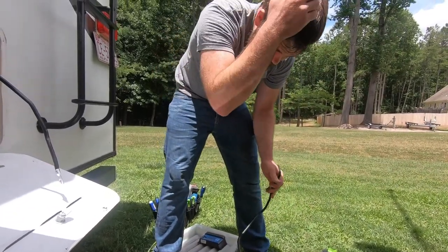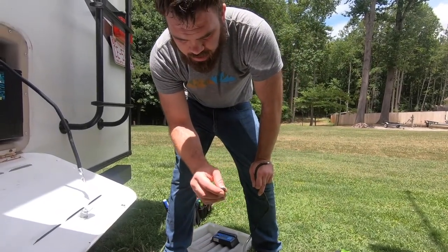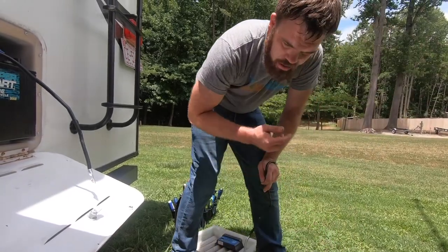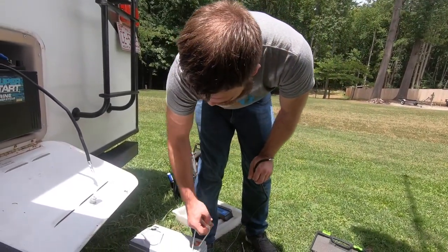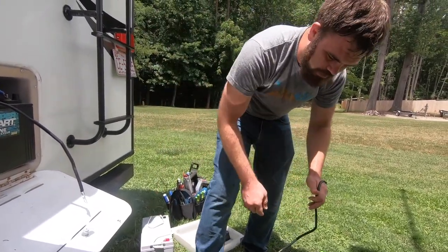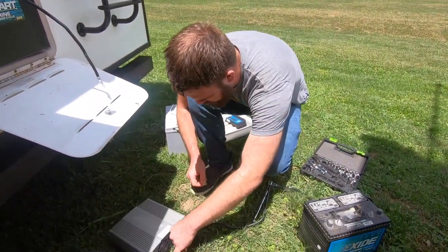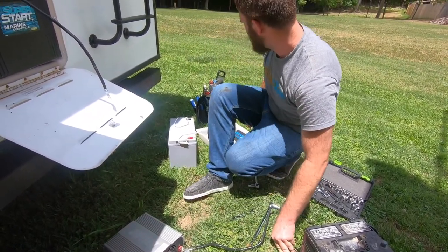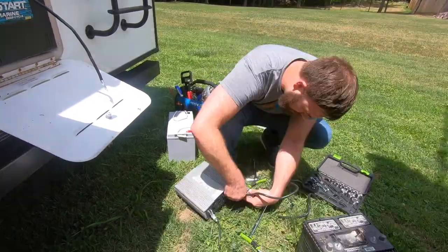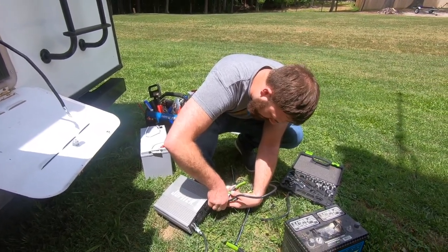When you go to your inverter on the positive side you always need to use one of these fuses. This is a 175-amp fuse - that's plenty for this job. The idea is, if something happens and you get an overcurrent to the inverter, you don't want to start a fire - you want that fuse to blow first. Just a little tip there. Not that I've ever had something like that happen, but you never know.